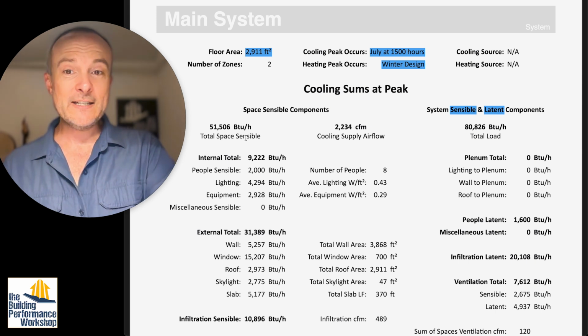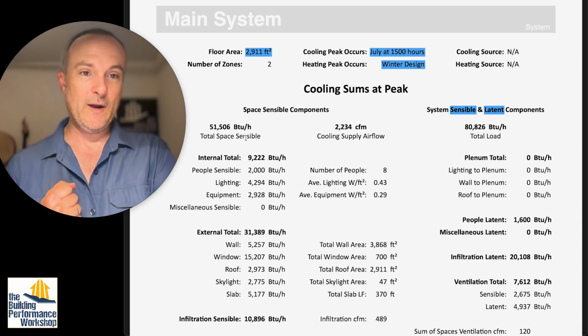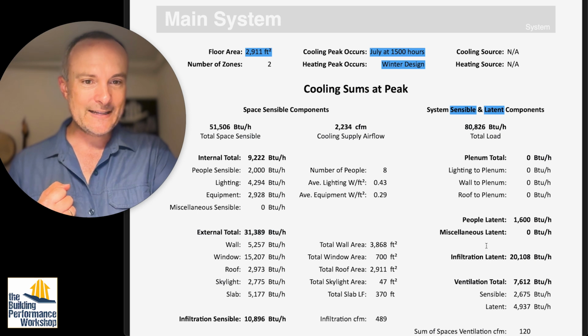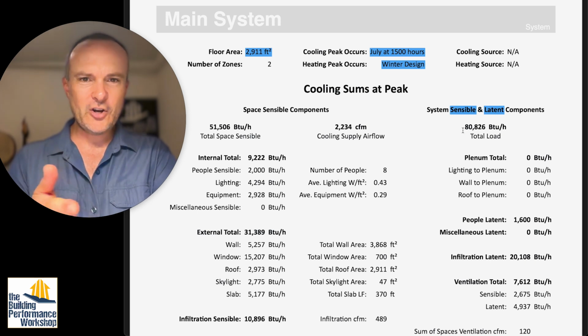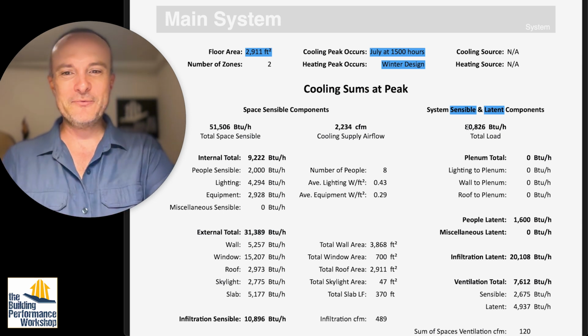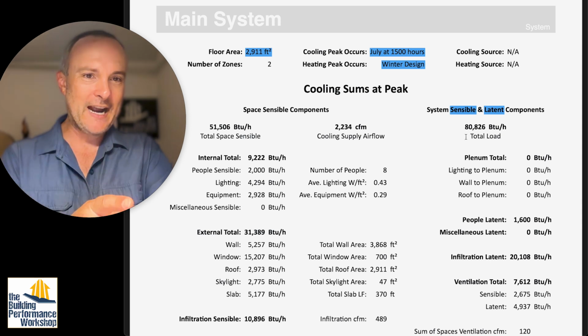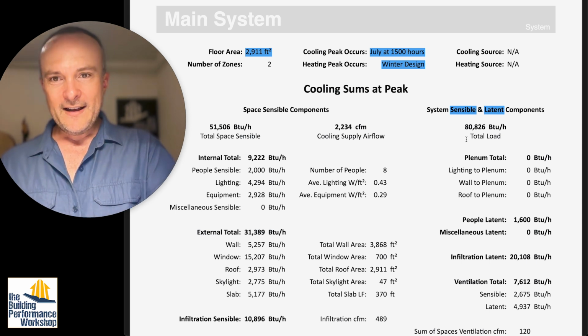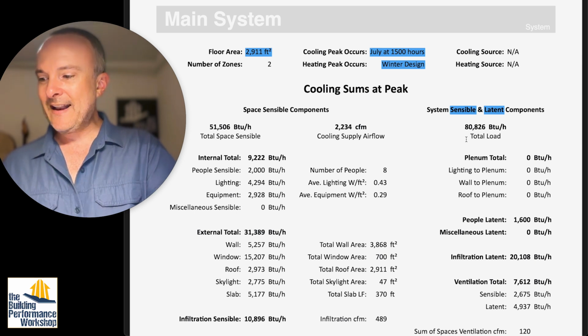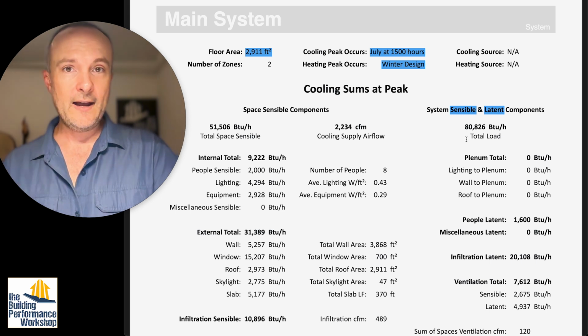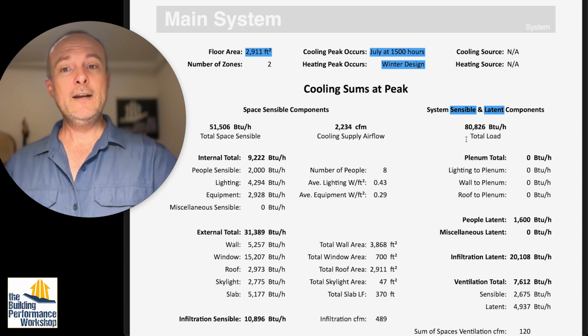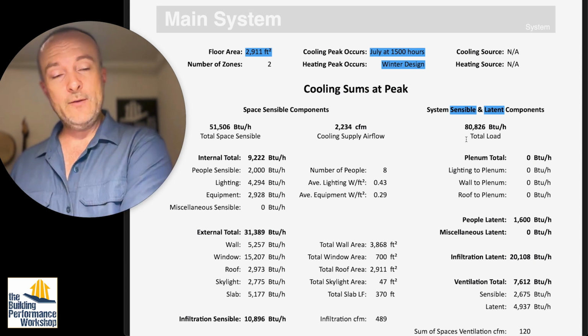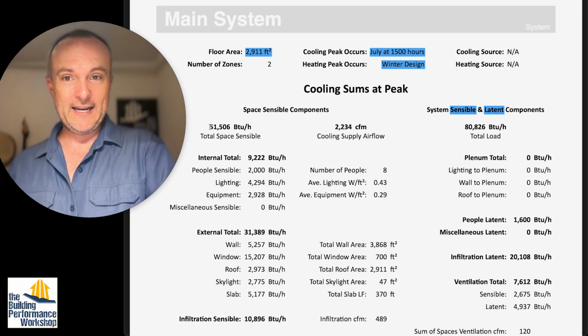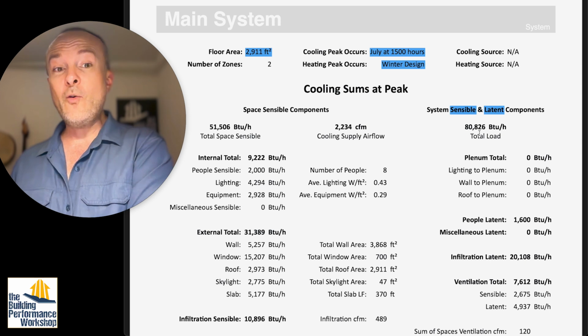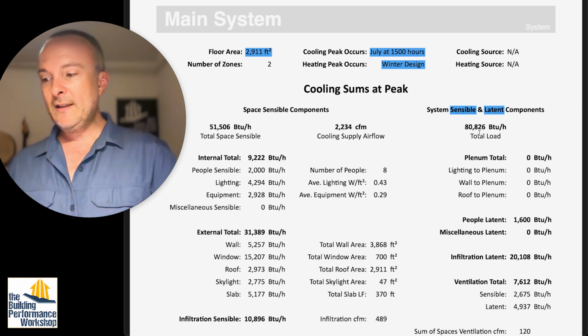So we've got a total sensible of 51,500, a half sensible heat that's being added to this house that we're going to need to take away. And we've got a total latent over here, the total, and again, this is typical of software, they're not going to give us exactly what the number is. So you subtract 80,826, you take 51,506 out of that. The latent is 29,000 BTUs. So that's quite a split. Normally, if you take 29,320, which is the latent heat remainder between this and this, and we divide that into the total, which is 80,826, we are left with a really interesting number.